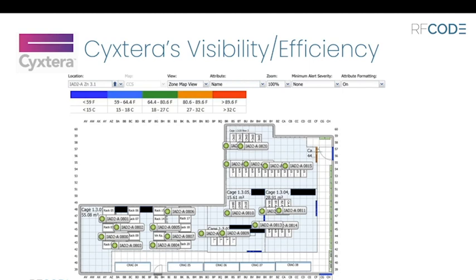Just as an example, and this happened just recently, we had a cooling event at one of our major centers. We logged into Centerscape while on the incident call, and as the ops team worked the issue, we could see the environmentals respond live throughout that center and immediately report areas not responding for additional mitigation. Literally, we had people from around the world logged into this screen, simultaneously observing the event recovery in a live fashion.